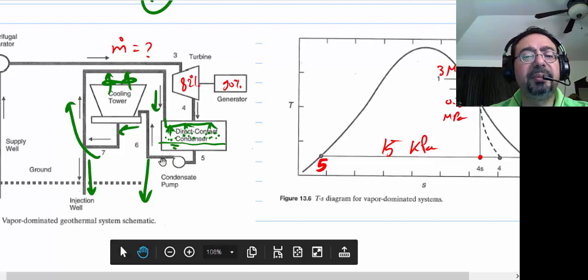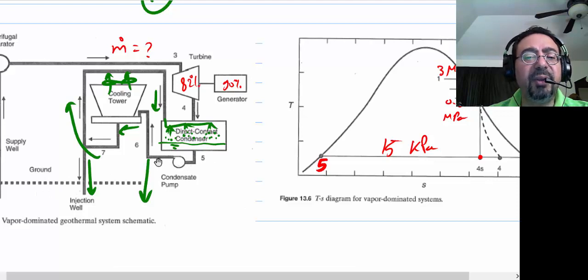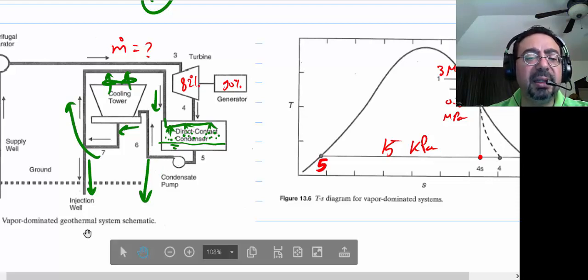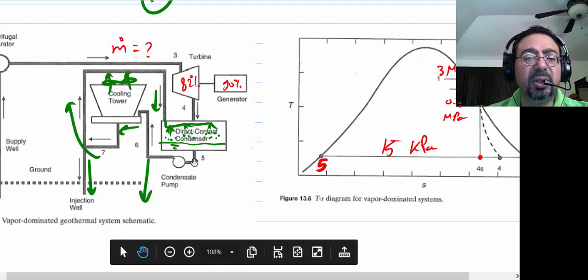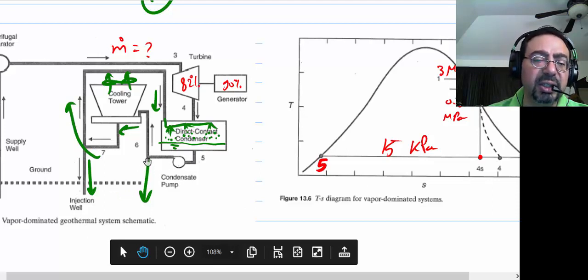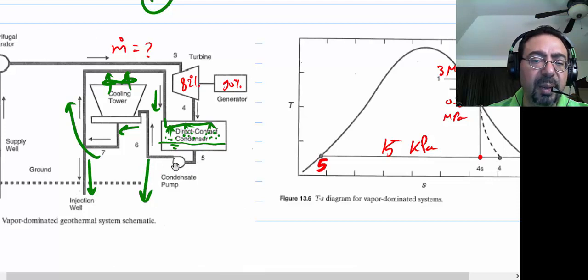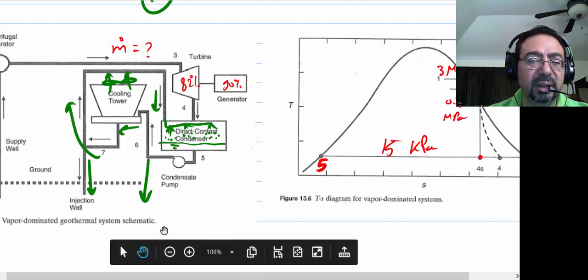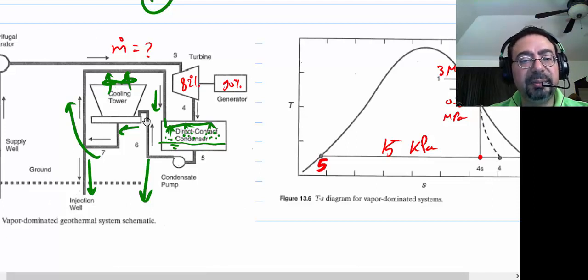In the book it's confusing because you would think he's actually cooling the water first, then after it's cold, sending it into the injection well. A better choice would be to just inject it directly after pumping it. Why would we have to cool it? Let's send it hot. It's kind of like really saving the heat source, and also we don't get any benefit by heating the air, and we don't need to heat all that water.